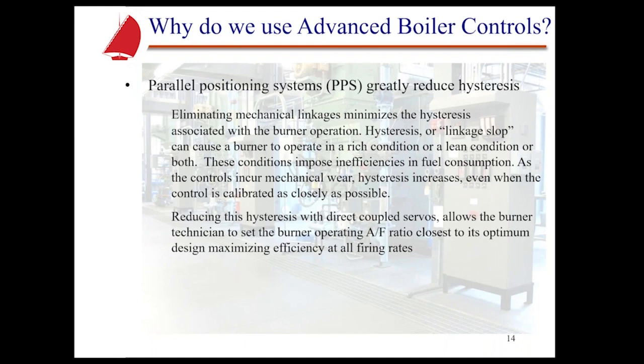As I mentioned before, and it's important, the parallel positioning systems really reduce the hysteresis. When we reduce that hysteresis, we reduce the amount of, if you will, slop in that particular operation. That imposes inefficiencies in the fuel consumption, and quite honestly, as they wear, it's going to increase again. So by reducing this hysteresis with direct coupled servos, we allow that burner technician to set that burner operation to its closest optimum design and maximize the efficiency at all firing rates. I repeat that because that's where we really gain so much advantage by going to a parallel positioning system, by being able to really tighten up that air-fuel ratio across the firing rate range.